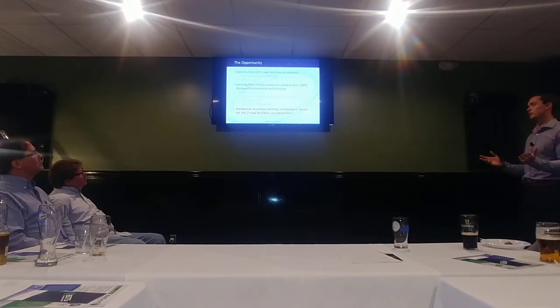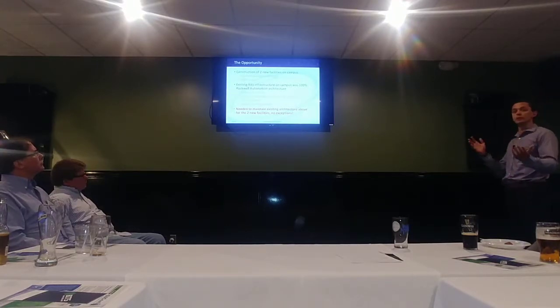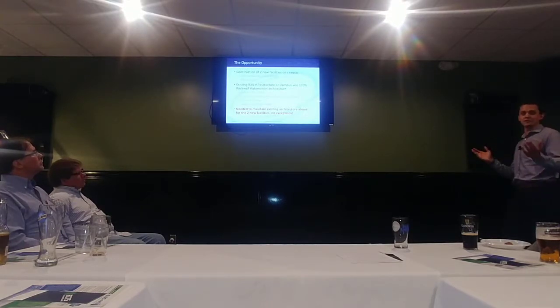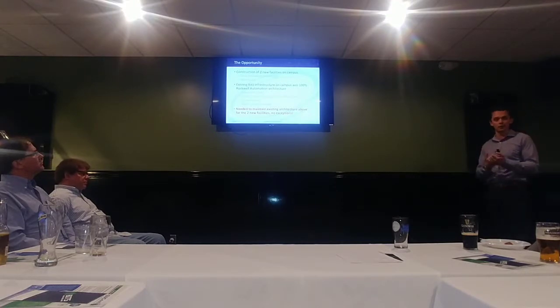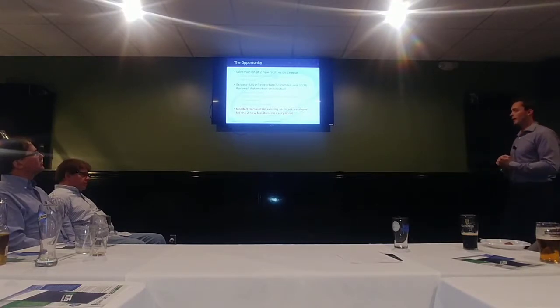The existing infrastructure on campus was 100% Rockwell Automation architecture. So they had 3 or 4 buildings in place already. Someone had sold them back the day that a SCADA system was the best way to go, and they have this huge Rockwell SCADA architecture everywhere, and that's what they wanted to move forward with. So they had FactoryTalk, SCADA system, all of their BAS control was through their controller, CompactLogix controllers. They had a PI data historian, they used Win911 for alarming, so they had a full-blown SCADA.